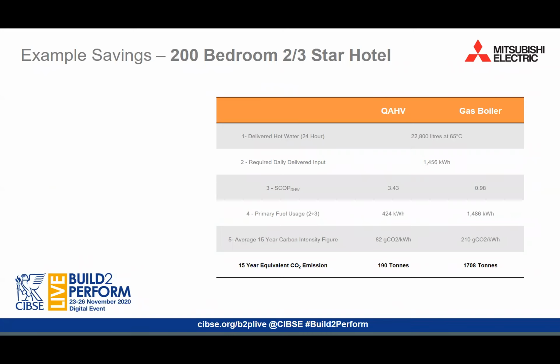So by using this daily demand figure of 22,800 litres, we can calculate the required kilowatt hours to move that amount of water from 10 degrees to 65 degrees, as shown in line 2 at a value of 1,456 kilowatt hours. Now, considering the seasonal efficiencies of QAHV and gas boilers to be 3.43 and 0.98 respectively, we can calculate the primary fuel used to generate the daily demand. These figures are 424 and 1,486 kilowatt hours for QAHV and gas boilers respectively.